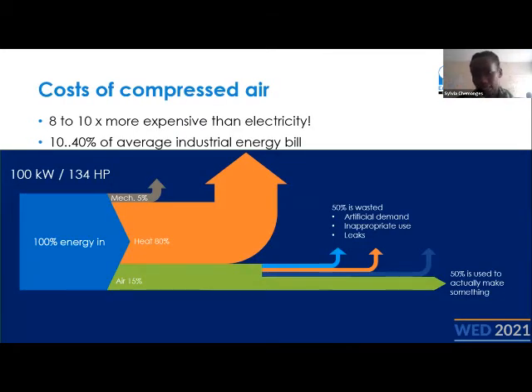Just to show you how inefficient compressed air generation can be, take for example a 100 kilowatt compressor. We put in 100 kilowatts of energy. 85% of that energy will be lost as a result of heat and mechanical losses. So only 15% of the 100 kilowatts that you put in is what is going to be used to generate compressed air. But because a lot of people don't understand the system, they may not give it the attention it deserves, and 50% of the compressed air generated is going to be lost as a result of leaks, maybe inappropriate uses, where you might meet people cleaning themselves with compressed air in an industry, or artificial demand whereby pressure tends to increase in the system, but we'll get to it in more detail later. So with that, we realize that compressed air has a high potential for energy savings.